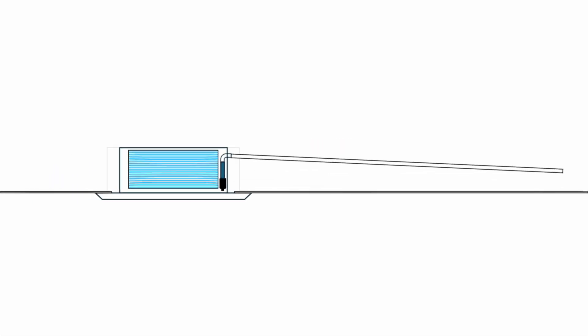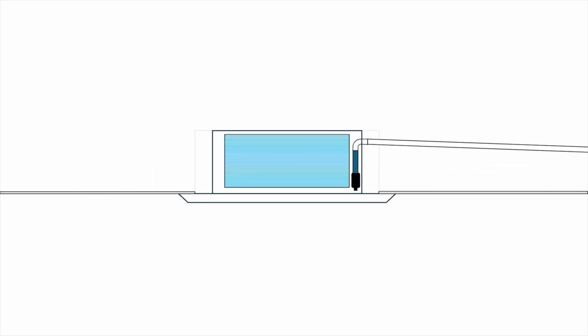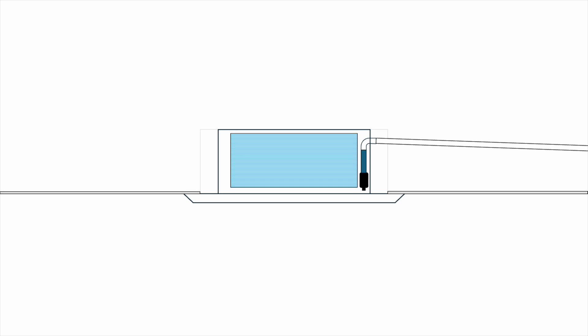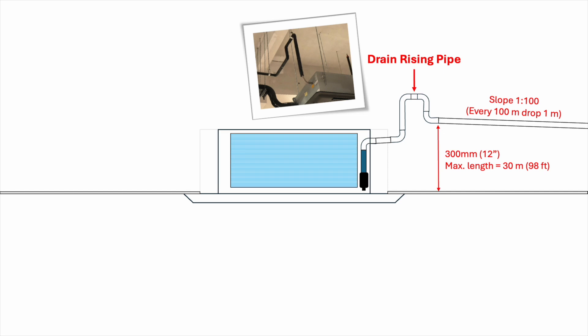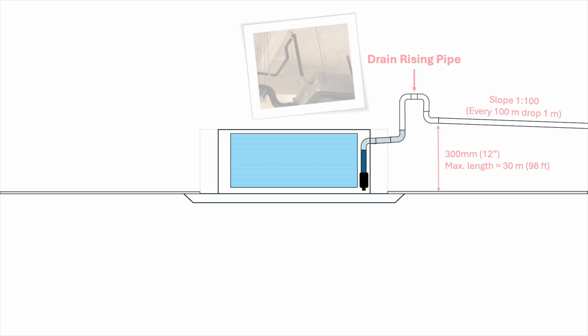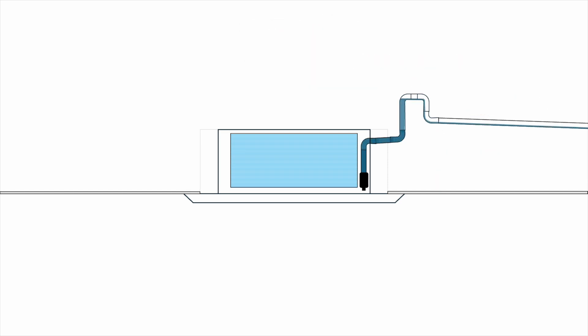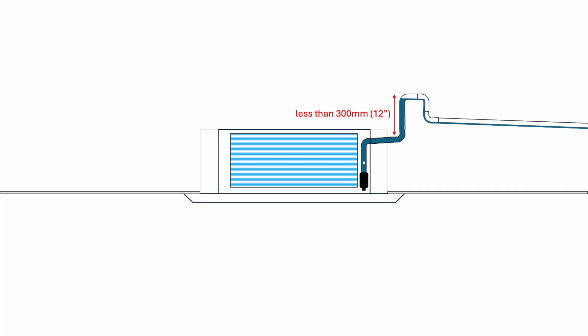This is where the second type of drain connection comes in. We can raise the drain pipe to increase the initial height of the slope. If the height of the drain pipe is increased to 300mm or 12 inches, the maximum length can be extended to 30m or almost 100 feet. However, the maximum height that can be raised is usually not more than 300mm or 12 inches. Raising the drain pipe can also help reduce the noise produced by the drain pump. So that's for the drain system.